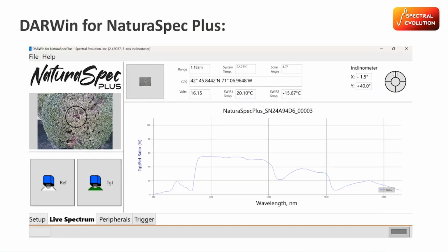So this is what our new interface looks like using the Naturaspec Plus. And so as you can see, we have a rangefinder. Up at the top, all of that metadata is recorded. And on the left here, we have a live camera field of view. So this is the view of the camera. It's not a stagnant image. And this black circle is actually drawn on the camera based on how far the target is. So we have big buttons for ease of operation in the field, the inclinometer on the top right, as well as the rangefinder, system temp, solar angle, volts, and then detector temperatures and internal temperatures, so that you can monitor the conditions of your instrument while you're out in the field.